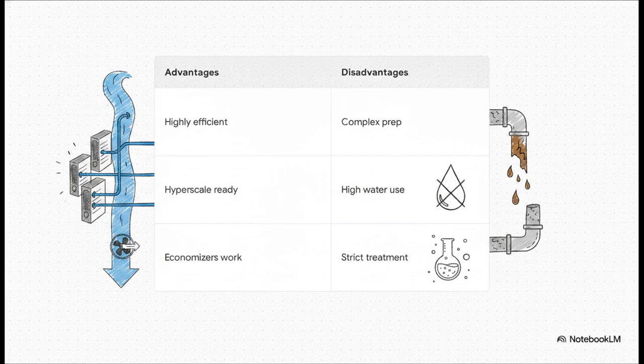Because it can move large amounts of heat so effectively, these systems are absolutely perfect for high-density environments. Plus, in cooler weather, you can run economizers, basically using the cooling towers to partially replace mechanical refrigeration, which boosts efficiency even higher. But the downsides are pretty serious.